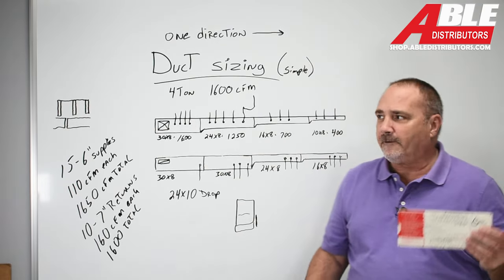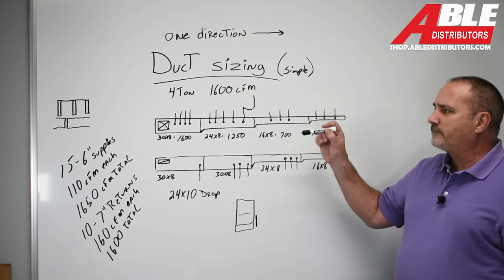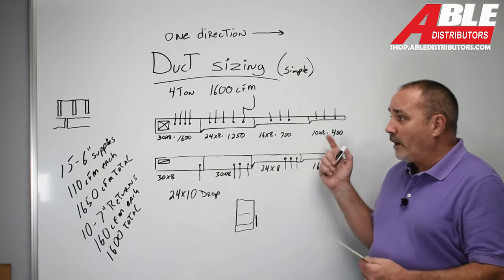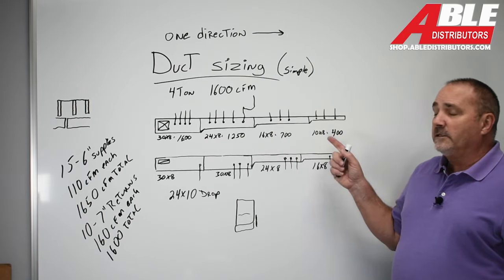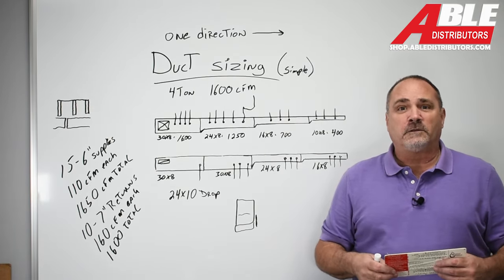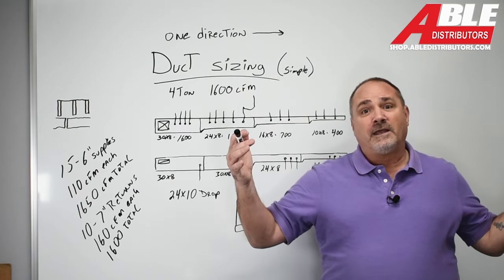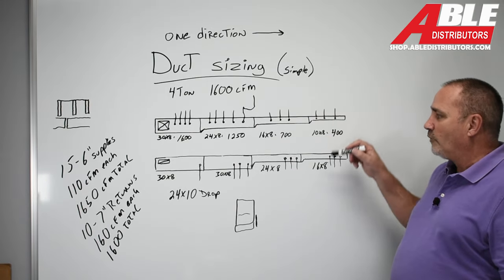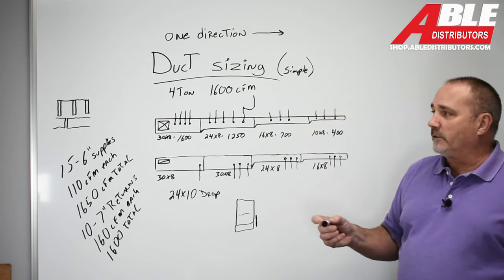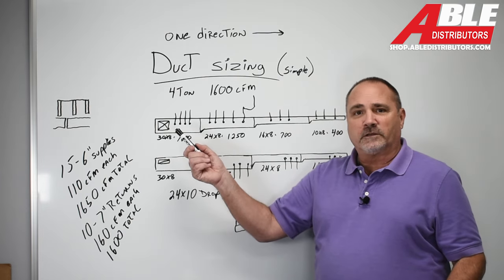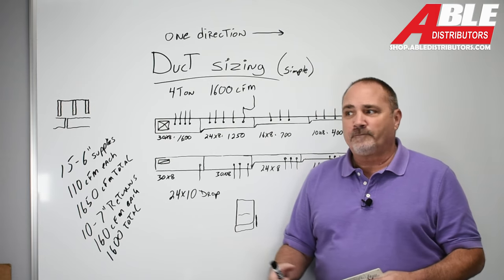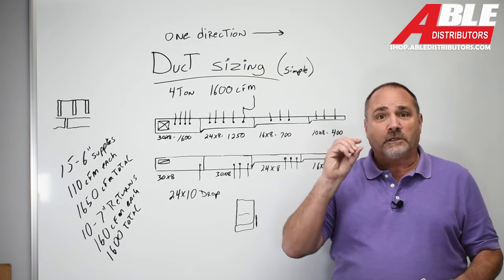All this work with a duct-ulator and your volume and your velocity, it's all about making sure that the furnace can do its job. It can do the air changes, it can move enough air to cool the house and not overheat that furnace. So if you follow this, you're going to be there. Yes, if you have the time and the energy to dive deep into the manual D, get the book and actually figure things out, it's a great thing. But literally you'd have to go to the house, kind of map it out, figure out how many elbows you're going to have on each run, what your longest run for the supply and return is going to be, what the static, how many feet that actually adds up to be. And once you start doing that, you're going to realize the numbers are astounding. Just from that plenum to the ductwork could be 80 feet, just for that opening. It's crazy when you really start seeing how the ductwork feet adds up. So this will get you there. This simple way, it'll get you really close. It'll get the system to work.